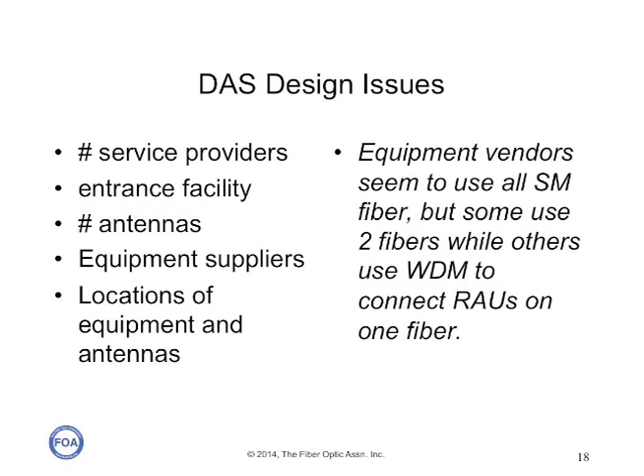There are a number of factors to consider in designing a DAS. Neutral host systems may have to accommodate four or more service providers, so entrance facilities must be designed to allow adequate entrance conduits and space for equipment. AT&T recommends approximately 3 by 10 meters (10 by 30 feet) for the entrance facility and providing 200-amp service for the head-end electronics. Antennas are generally shared by service providers, so only one set of antennas and remote antenna units are required inside the building. They may be connected on two fibers for full duplex transmission, while other systems use wavelength division multiplexing to connect on one fiber.